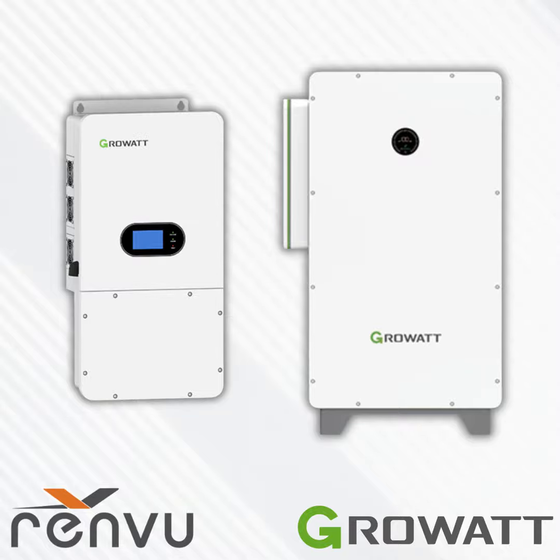You can see that we can do this in parallel installation as well. And the only thing that changes on a parallel installation is you have an extra inverter, extra batteries, etc. And then instead of the meter, we replace that component with what we call a smart energy manager. And that's our SCMX, which is shown in the top right there. The SCMX just does some balance controls between the inverters and monitors all the downstream inverters to make sure that they're all happy with each other. In this configuration, since it's purely on grid, we have a 6 inverter maximum, so this could go up to 600 kilowatts.